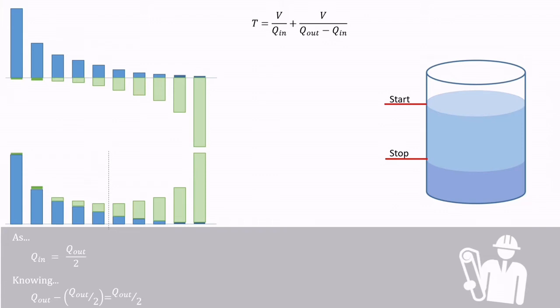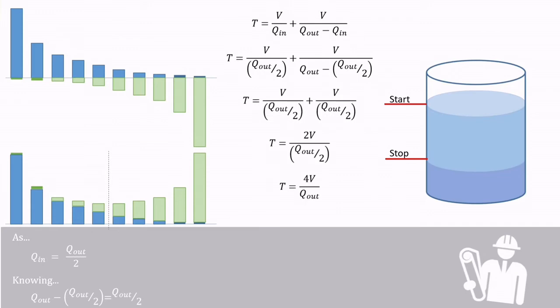Now as we discussed, the fastest time between starts is when flow in is half of the flow out, so the formula can be rearranged to this. With a few more rearrangements, you eventually end up with time is four lots of volume over flow out. Now to make the best use of this, we're trying to find a minimum operating volume, which is flow and time over four.